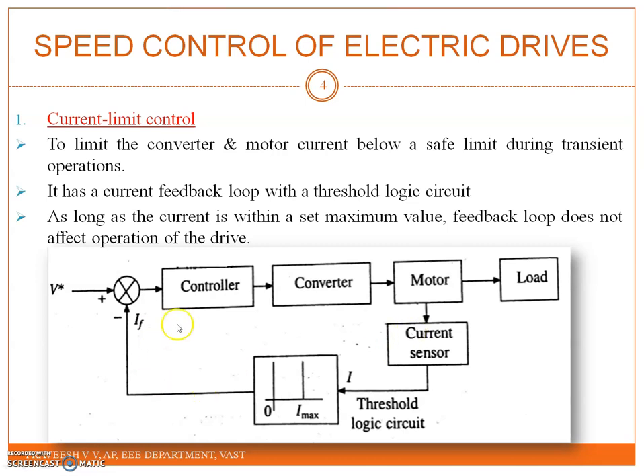This is the block diagram representation of the converter-motor-load system. The motor current is sensed and fed to a threshold logic circuit, which detects the error and sets the reference for the current controller, which then controls the converter operation to keep the motor current within safe operating limits.